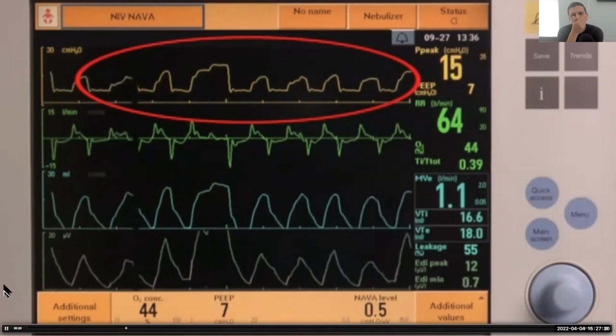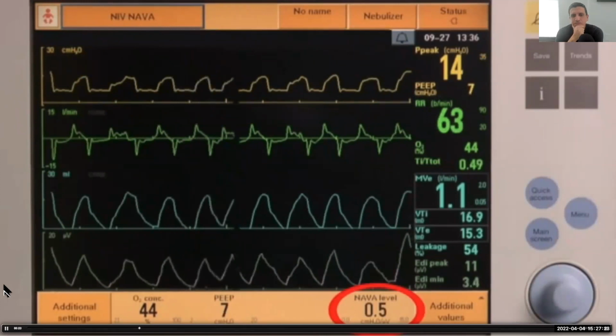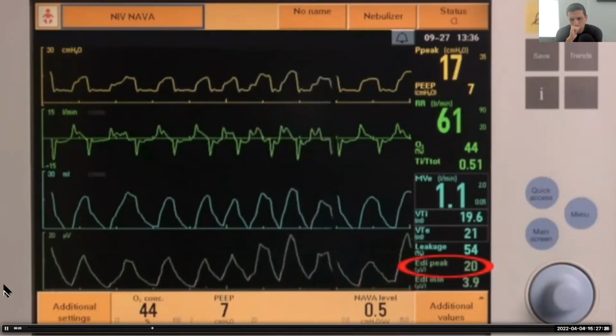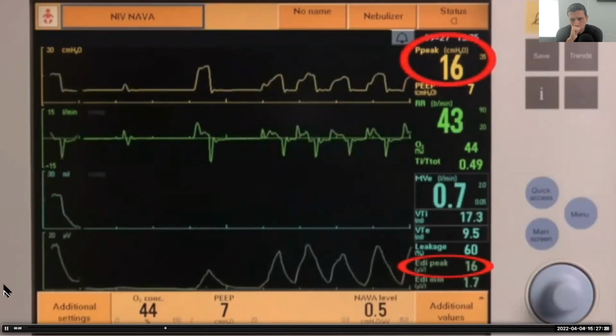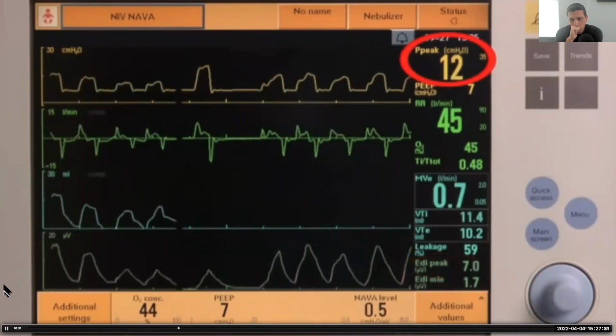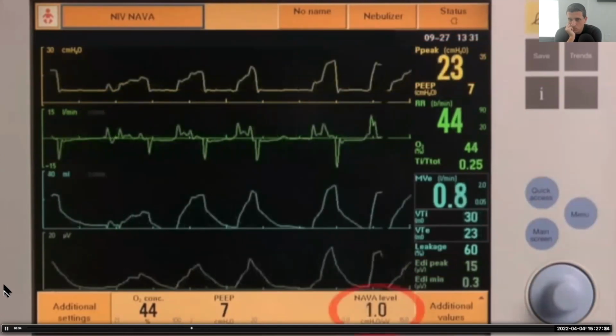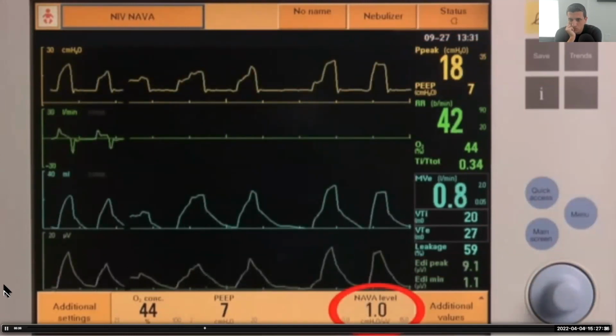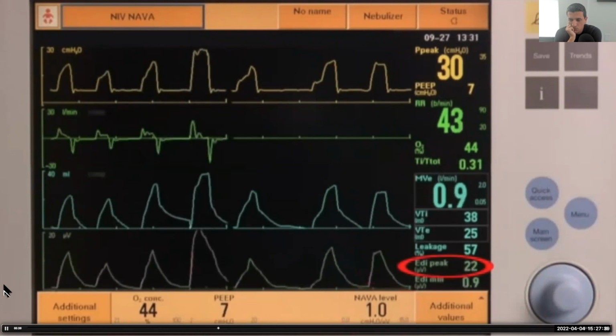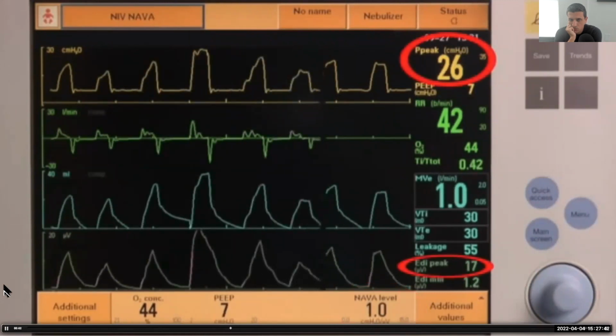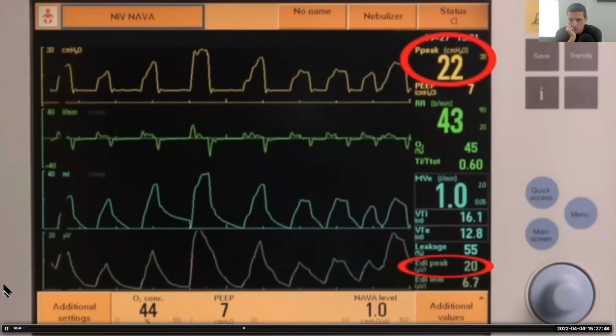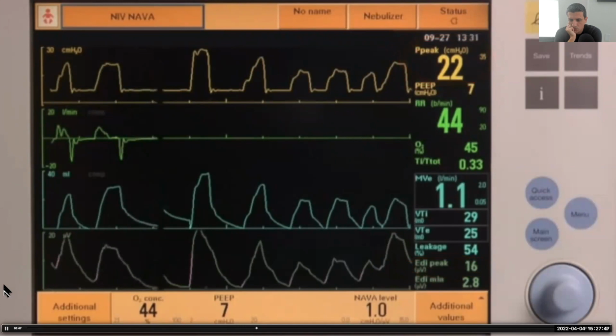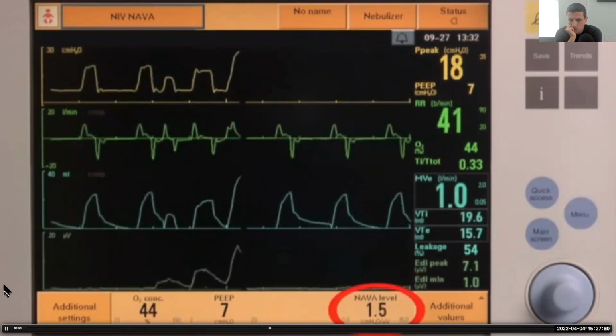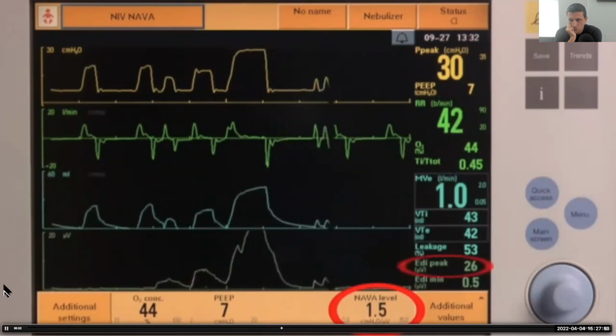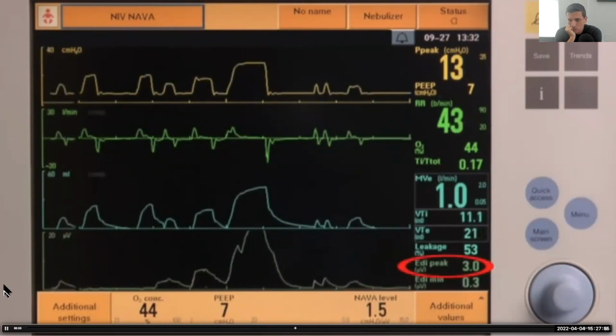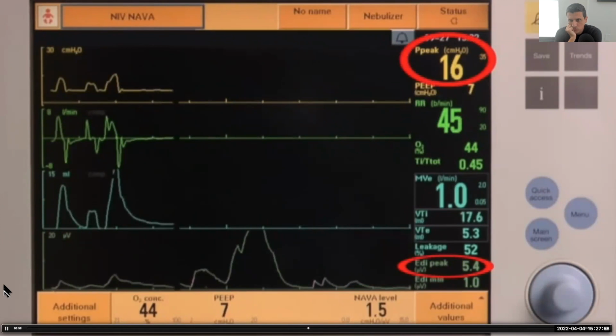At a NAVA level of 0.5, this neonate has EDI peaks of 10 to 20 microvolts, producing average peak pressures of 10 to 15 centimeters of water. When the NAVA level is increased to 1, the EDI peaks remain 10 to 20 microvolts, but the average peak pressure increases to 15 to 20 centimeters of water. At the NAVA level of 1.5, EDI peaks now decrease to 4 to 9 microvolts, and average peak pressure ranges from 15 to 20 centimeters of water.